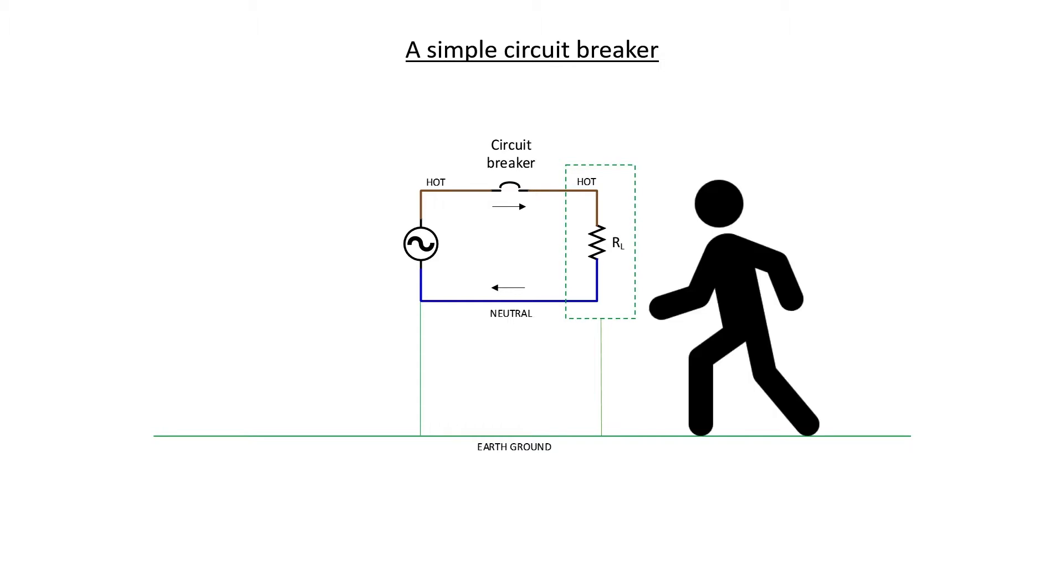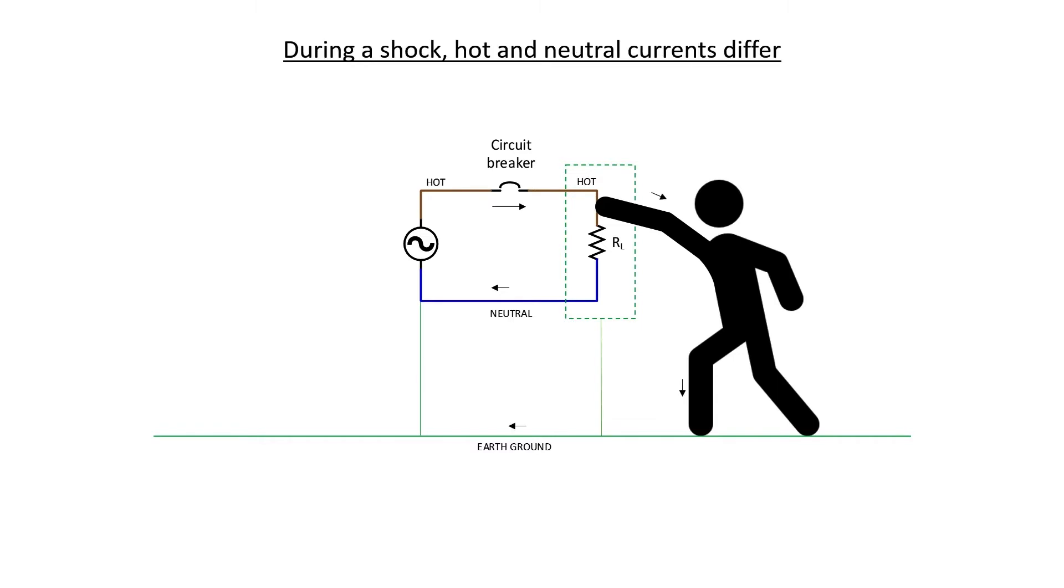Imagine a person comes along and somehow makes contact with the hot side of that circuit, which in this case is not grounded. At typical line voltages, the person is going to get shocked. But how can the system guard against it? One way to guard against it is to notice that the current flowing out through the hot side, through the circuit breaker, is not equal to the current flowing back through the neutral. The person has set up a ground fault. When somebody is getting shocked here, some of the current goes through the person and back through the earth ground, rather than through the neutral.